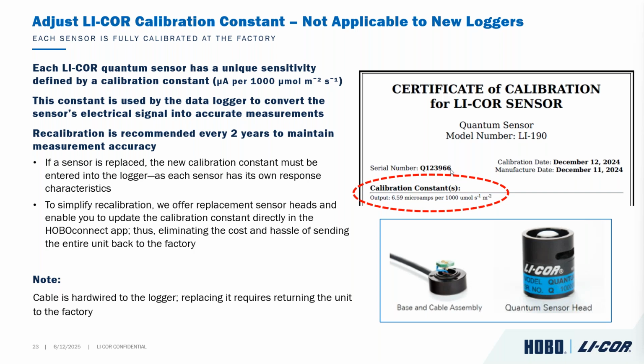We highly recommend getting these sensors recalibrated, again, just due to the nature of how the sensor work, and once that sensor gets recalibrated, it will generate a new calibration constant, and if it's at the factory, we will again burn, quote unquote, that value into the data logger. That said, we do realize that it is not always possible for users to be able to send back their loggers to get calibrated.